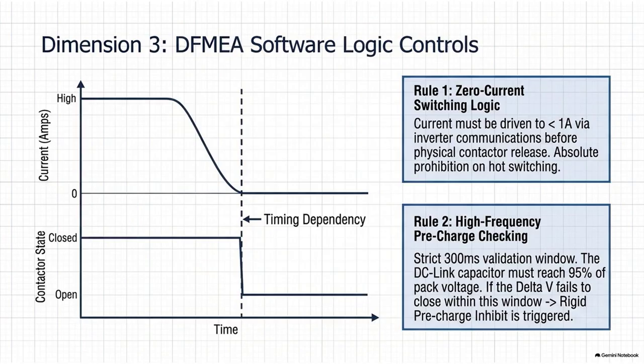That makes total logical sense for the shutdown sequence. But what about the power-on sequence? We spent a lot of time earlier discussing the pre-charge failure, the empty hydraulic accumulator, and the devastating inrush current. How does the software design actively protect against that specific threat? That is managed by a highly aggressive software loop known as the 300 millisecond pre-charge check. It is a game of high-frequency paranoid surveillance. Paranoid surveillance, I like that. It's true. When you press the brake pedal and initiate the power-on sequence, the BMS closes that small secondary pre-charge relay we discussed, letting the electricity slowly fill the inverter's massive capacitor through the restrictor resistor. The tiny bypass valve starts slowly filling the tank.